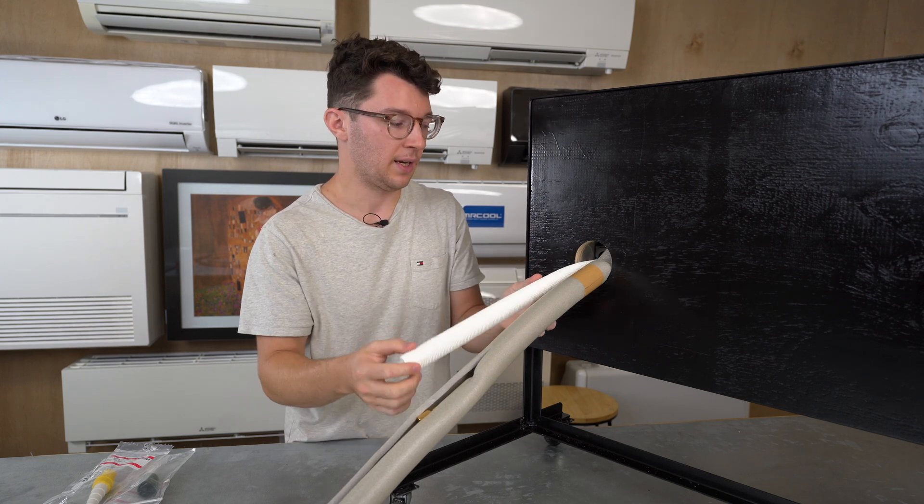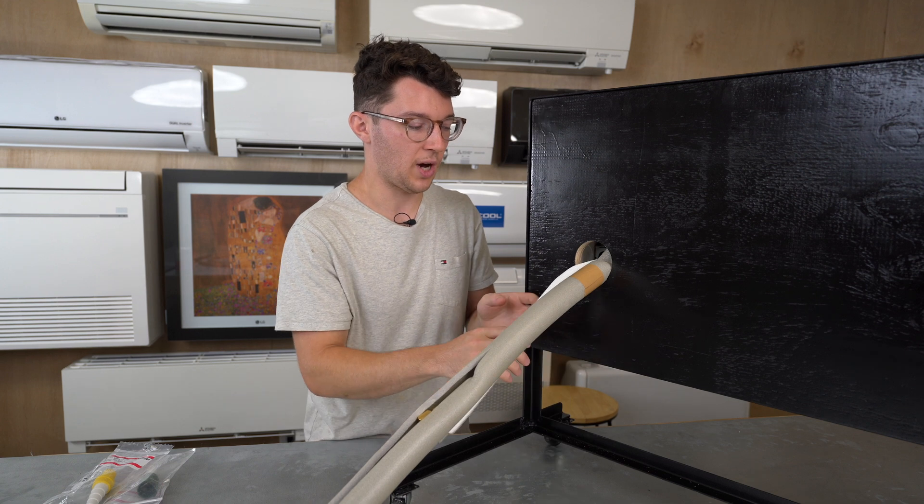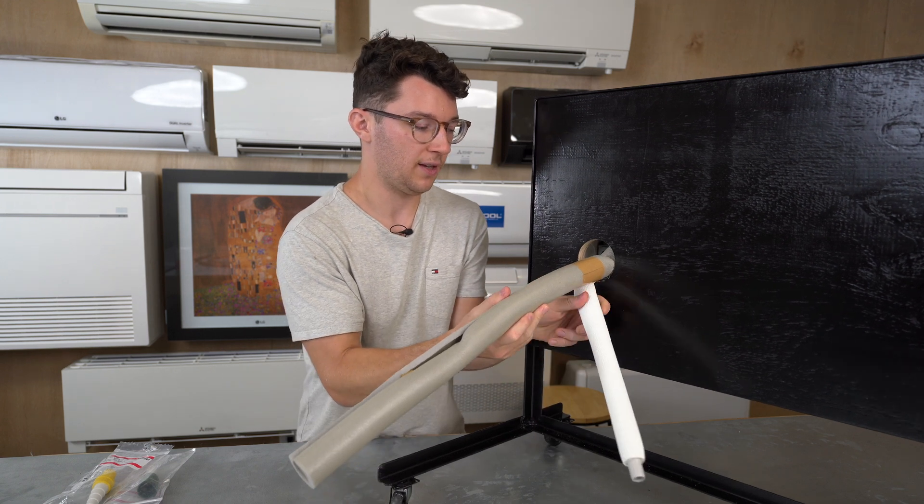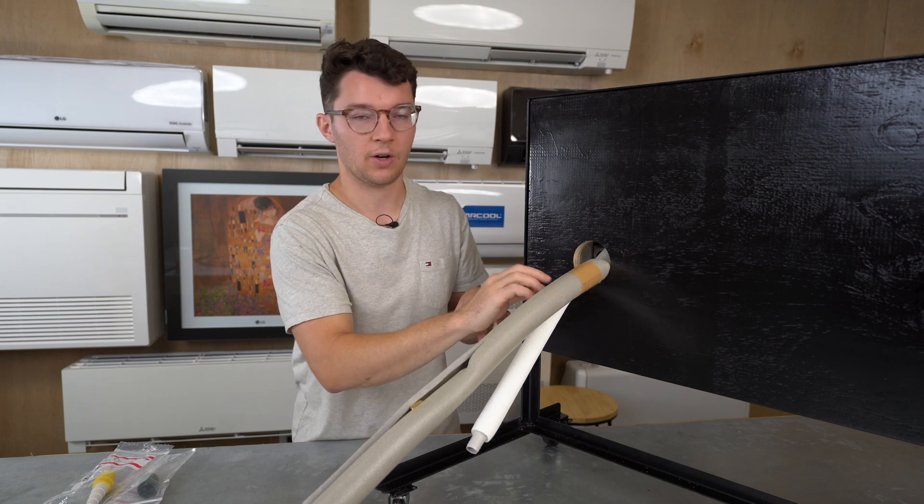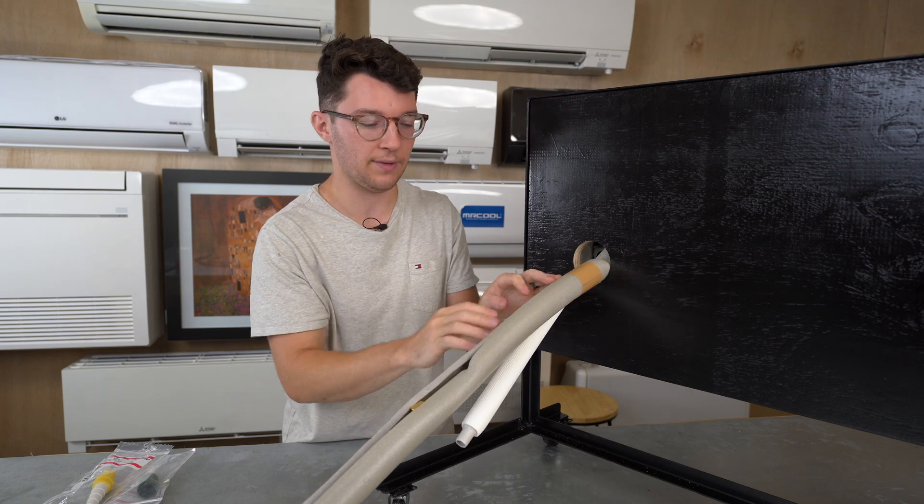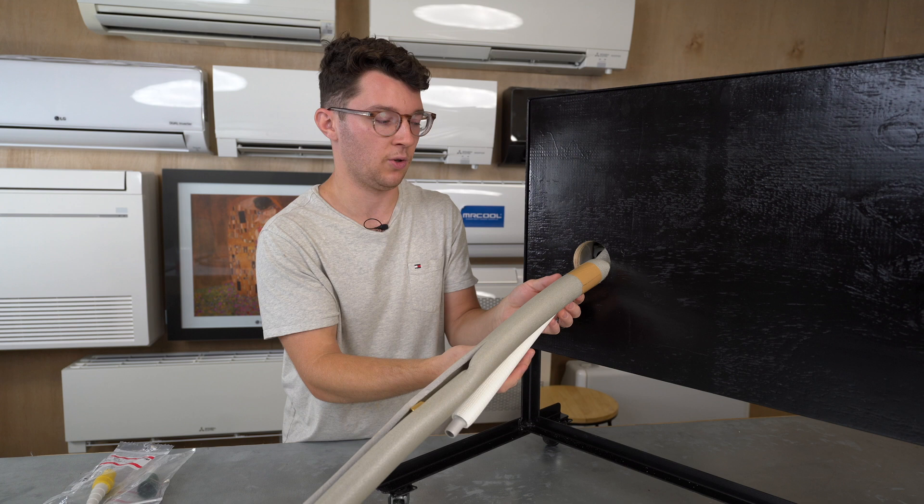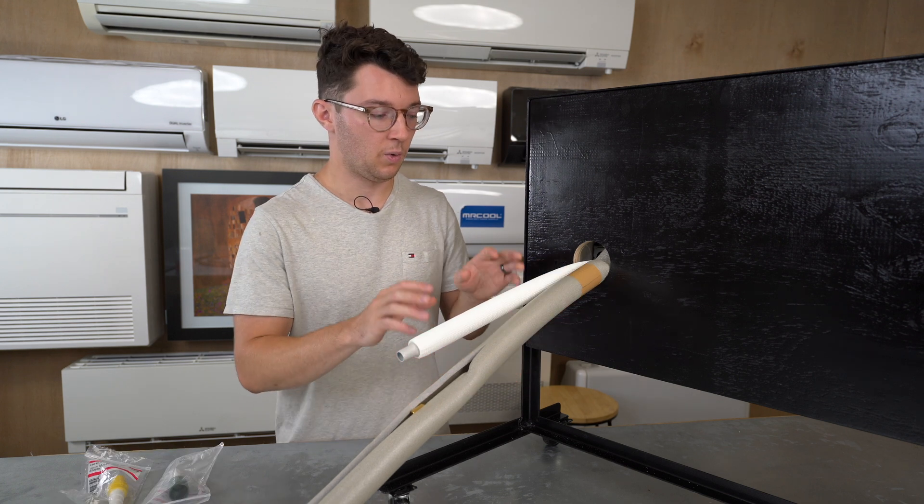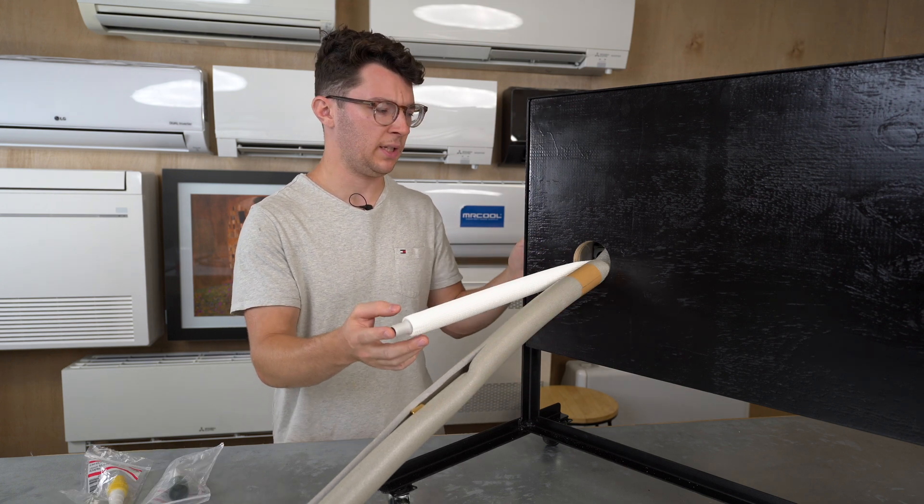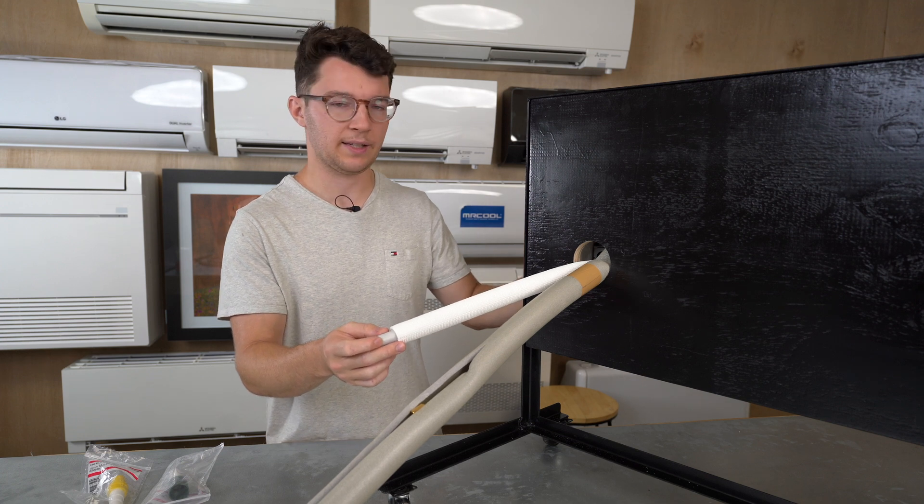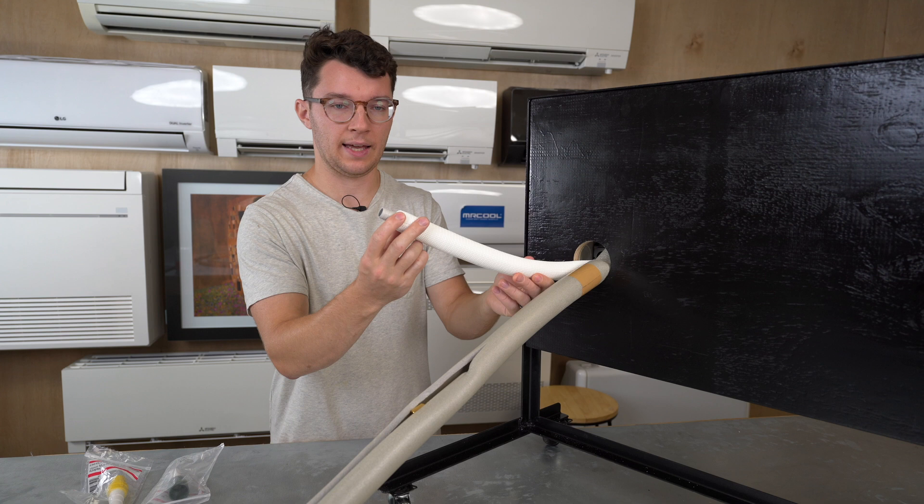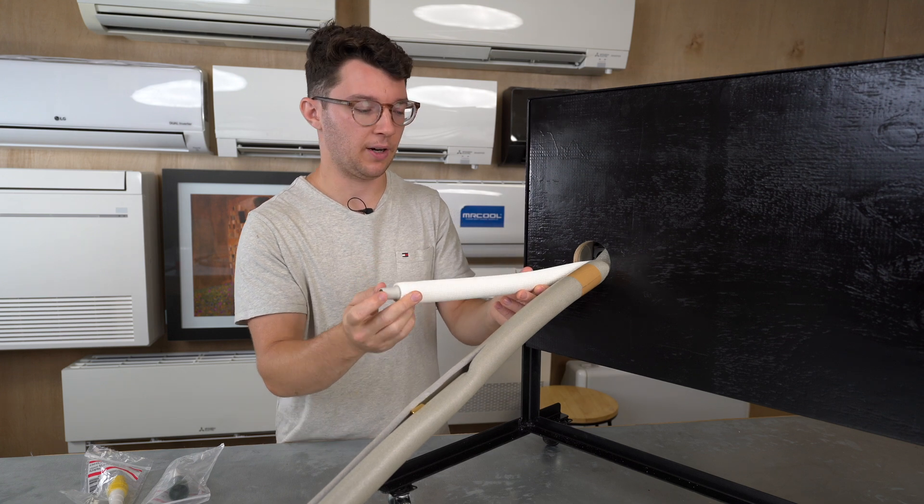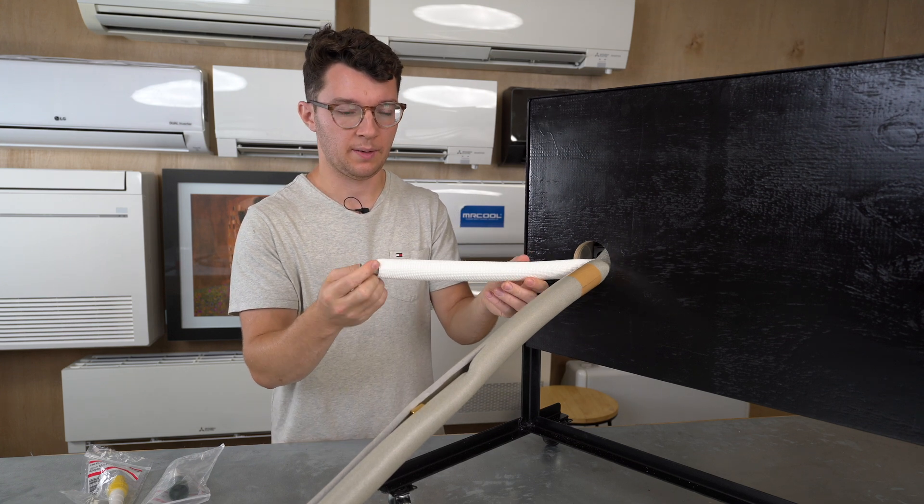This condensate hose can be directed down with gravity or on a horizontal slope, but making sure that your condensate hose is always underneath the refrigerant lines to make sure that you don't have any clogs.